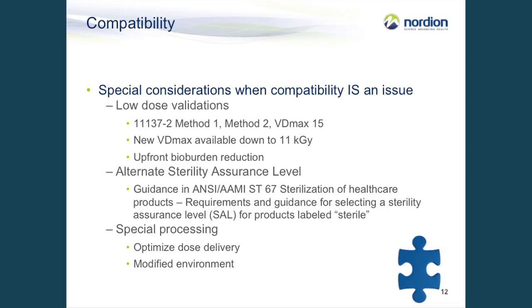For some particularly sensitive medical devices, perhaps combination devices or devices with very specialized materials, a sterility assurance level of 1 in a million can't be achieved by any sterilization method without damaging the product. In this case, there's also guidance available on choosing an alternate sterility assurance level, such as 1 in 100,000 or 1 in 10,000, which can significantly reduce the dose required while still allowing a product to be labeled sterile.